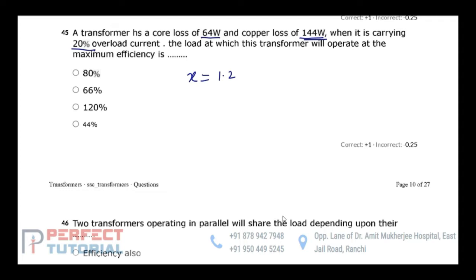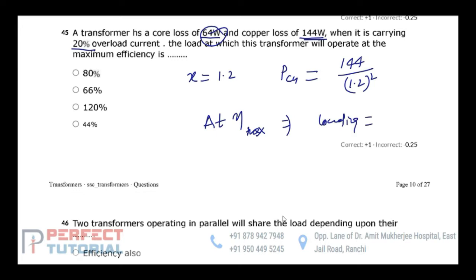Yes, you have to calculate the full load copper loss, that is PCU. The full load copper loss would be equal to the copper loss at x of full load divided by x square. PCU would be equal to 144 divided by 1.2 square, which is your full load copper loss. Now, full load copper loss you know, core loss you know, so you can determine the loading at which maximum efficiency occurs. So at eta max, the percentage load or loading is equal to square root of iron loss by full load copper loss. Iron loss is given as 64 and full load copper loss is 144 divided by 1.2 square, meaning 1.2 multiplied by 1.2. So it would give you 0.8, and percentage loading is equal to 80%. That should be the correct answer here.